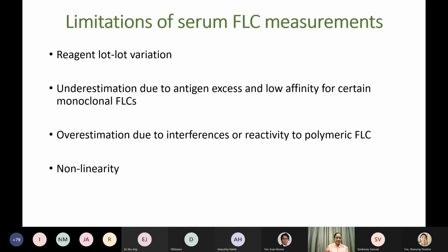Polyclonal batches of anti-serum reagents are subject to variation which can alter monoclonal free light chain reactivity. The results from different reagent lots could give different results. So it is important to verify the lot-to-lot variation before you change the lot numbers. Most of the time they are within acceptable range, but rarely we could see unacceptable differences between lots.